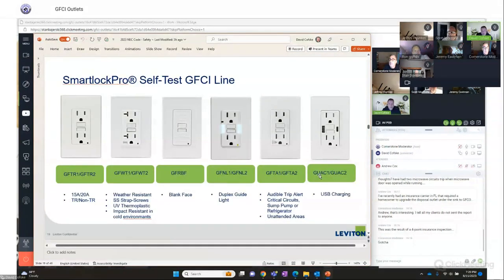And this is our current flavor of GFCI devices that we manufacture. Starting over to the left, this is your typical GFCI device. They were made in 15 and 20 amp, and they make them in tamper resistant and non-tamper resistant. If you guys are aware of tamper resistance, it's basically little doors on the devices to prevent kids from sticking things in there and getting the shock of their life. In residential applications, tamper resistant receptacles are the code. So you'll see them in houses because they've been there for a long time. They don't need to be upgraded unless you do something, then you're going to be forced to bring your whole house up to code.